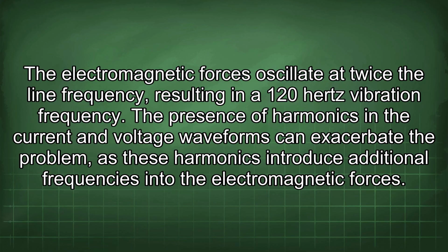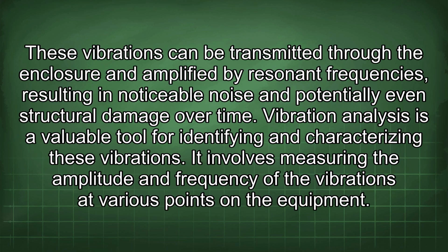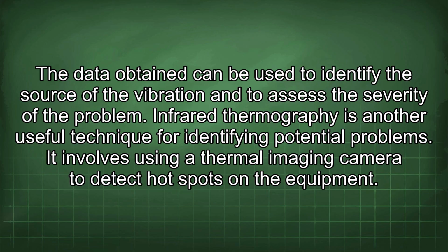The presence of harmonics in the current and voltage waveforms can exacerbate the problem, as these harmonics introduce additional frequencies into the electromagnetic forces. These vibrations can be transmitted through the enclosure and amplified by resonant frequencies, resulting in noticeable noise and potentially even structural damage over time. Vibration analysis is a valuable tool for identifying and characterizing these vibrations. It involves measuring the amplitude and frequency of the vibrations at various points on the equipment. The data obtained can be used to identify the source of the vibration and to assess the severity of the problem.